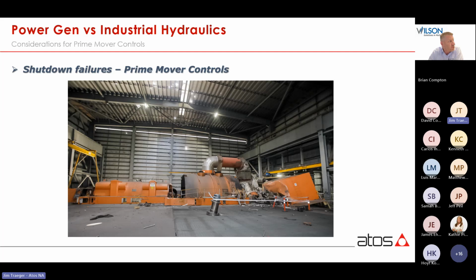And here's the aftermath of a steam turbine that went into sustained overspeed. And we can really see there's nowhere safe in the building as parts were thrown off. There's holes in the wall and the ceiling that were potentially blades from the turbine that punched through. We see there's a large part of the shaft embedded in the concrete.